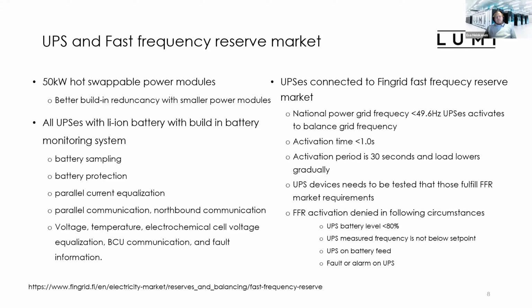About this fast frequency reserve market, it's procured by the Finnish national grid company called Fingrid to handle the low inertia situation. So in case of, for example, a high voltage link failure or us losing some power production in our national grid, when the national power grid frequency goes below 49.6 hertz, our UPSs activate to balance the grid frequency. The activation time needs to be below 1 second when this event happens on the national grid. And this activation period is 30 seconds, and the load lowers gradually. So it starts with full power and the load is gradually lowered during the 30 second period.